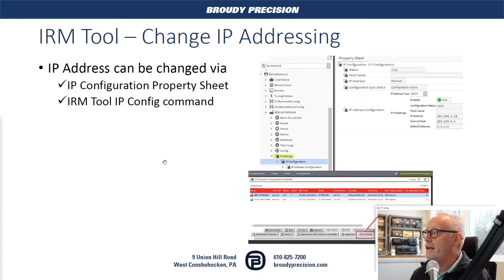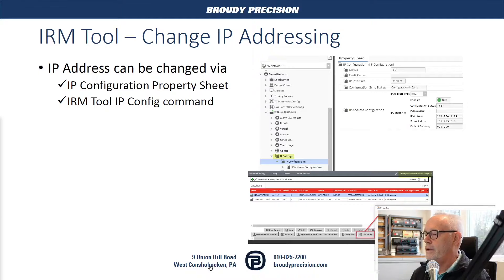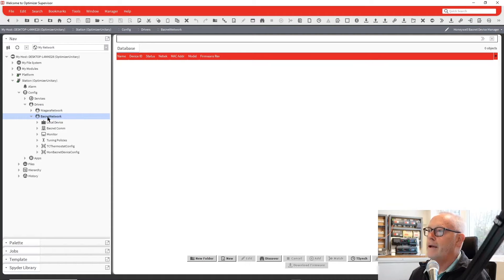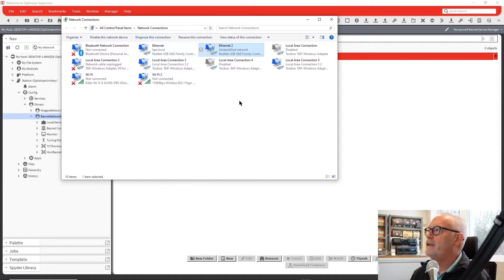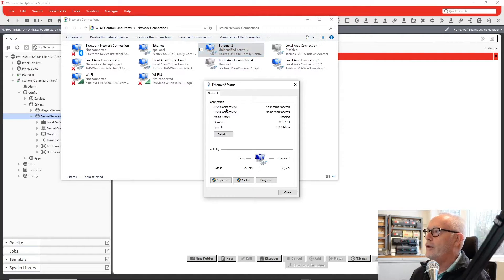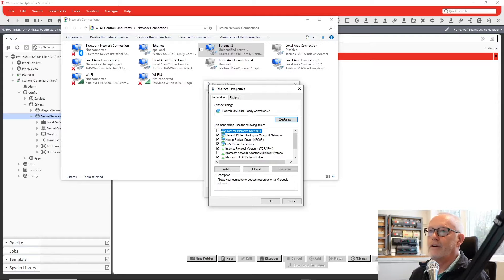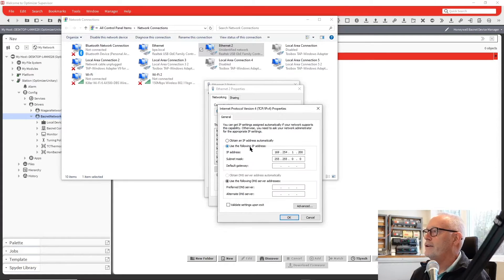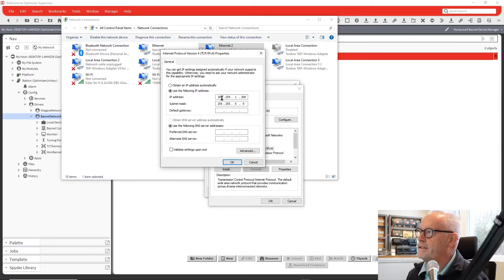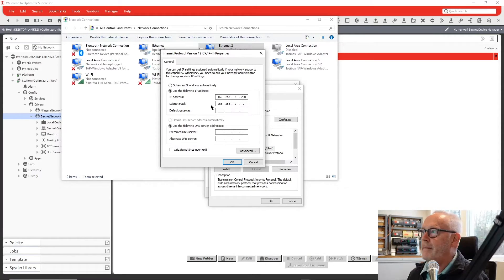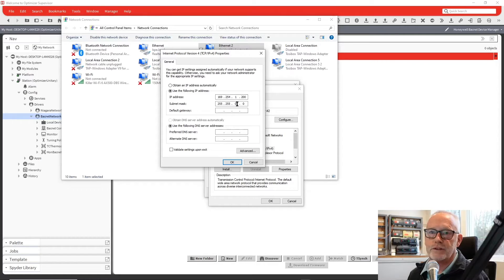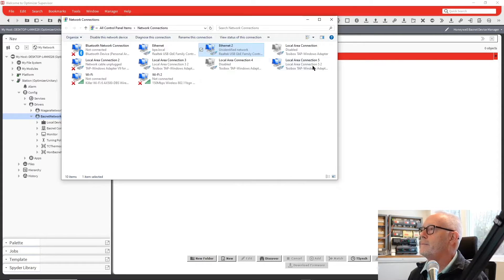From that, let's go ahead and look at the controller and look at the actual Niagara workbench. So if we go back in here, I have my network set up. Before we do that, let's double check a couple things. I will go into my Ethernet port on my computer, my NIC card, and verify that I have the addressing set properly. So I set my PC to 169.254.1.200. And again, the subnet mask, 255.255.0.0. So we're all set there.